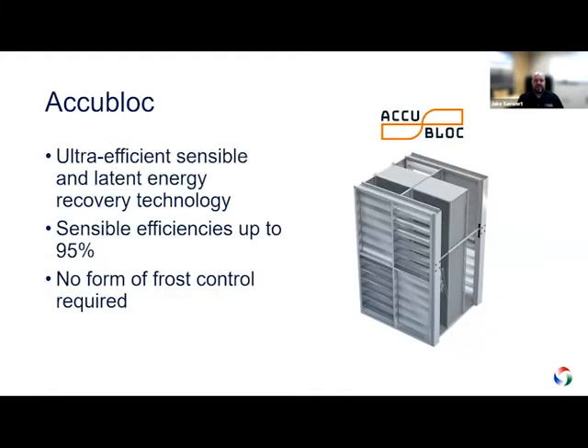What we're here to talk about today is the ACCUBLOC heat exchanger. This is a component that we're starting to use inside of our equipment. So this is not just an energy recovery device. The energy recovery unit is going to be part of a custom unit with package refrigeration, heating, controls, all of the things that make our units what they are. ACCUBLOC is an ultra efficient, sensible, and latent energy recovery device. It's capable of operating at sensible efficiencies up to 95%, and it does not require any form of frost control.